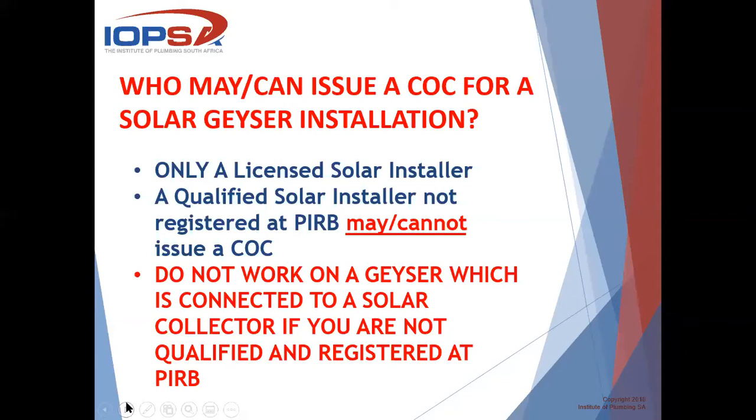You've got to upgrade this thing to comply with a standard. We cannot just leave it in a non-functioning or dangerous state. They've placed the responsibility on our shoulders too, that when we go there, we have to upgrade that system to comply to the minimum requirements. So that's the reason. You cannot go in and just say, I'm replacing a tank, and that's the end of my responsibility. It is actually not. And if you don't know what you're looking for, if you don't know what a tempering valve is, if you don't know where the connections must go and where the pumps must be, etc., you're not going to get it right. And this is the crux of the matter.